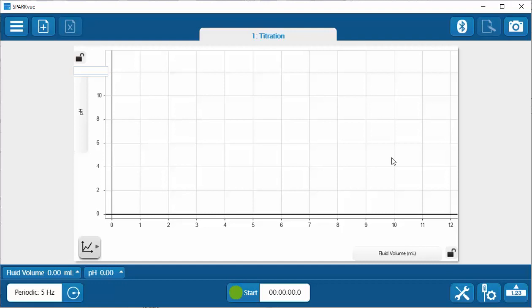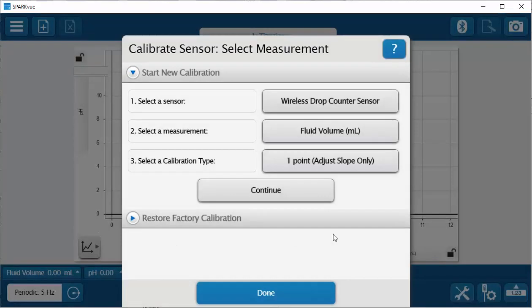In order to do the calibration, I'm going to select the live data display for fluid volume from the lower left-hand side. When I click on that, I'm going to click on Calibrate Measurement. This is going to do a one-point calibration, and everything will be preset on this screen, so I can click on Continue.